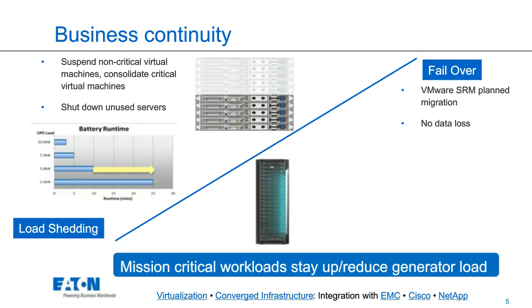It's going to consolidate the rest of the running virtual machines on fewer servers and then shut servers down. So in this example, we fixed it so that one half of the servers could shut off. Since we started out at 5 kW with 10 servers, we're down to 2.5 kW, or kilowatts, with 5 servers, therefore taking the battery runtime from 10 minutes to 25 minutes.